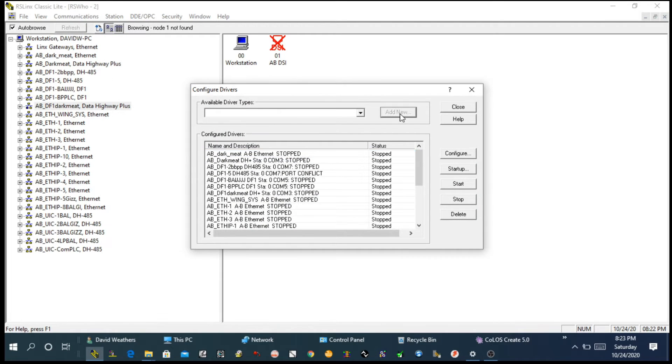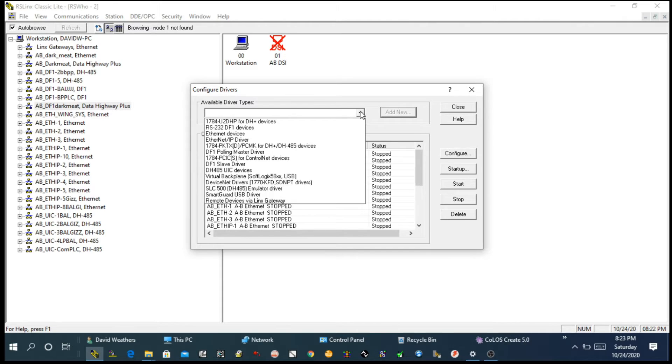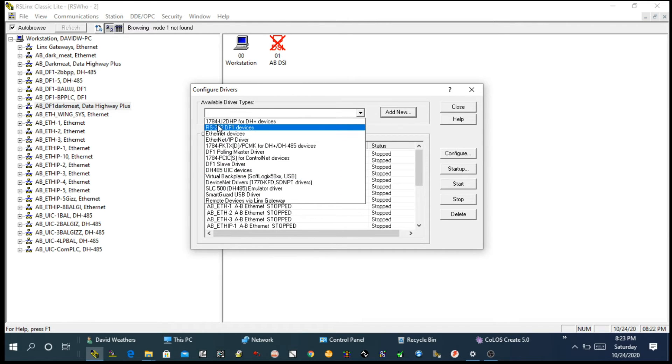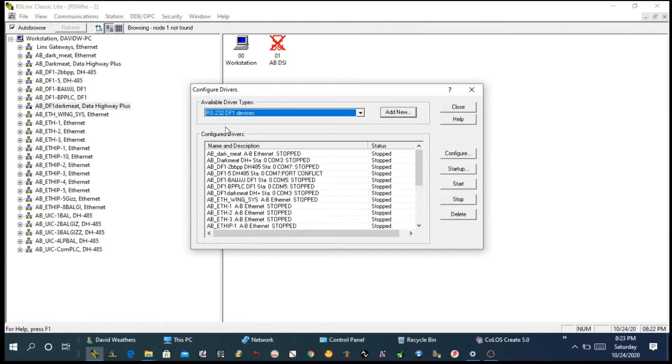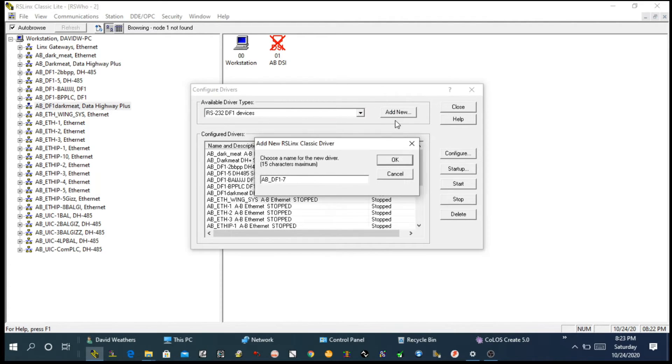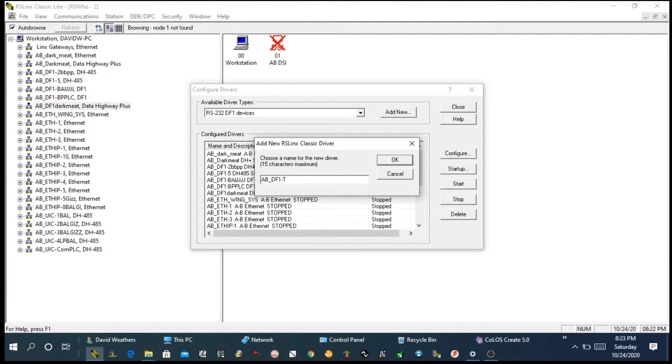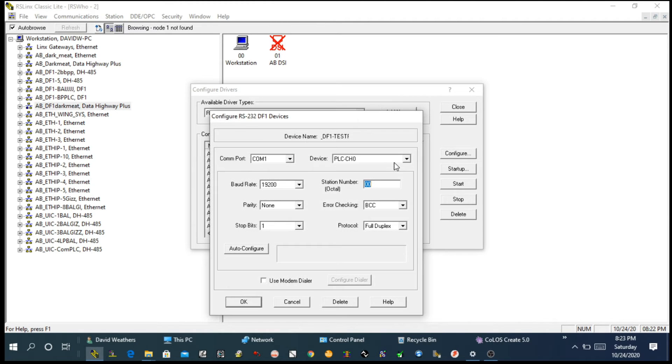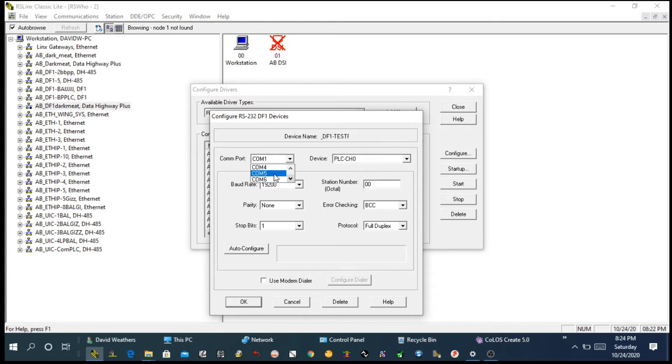From here we have to create a new driver. So I will click on this arrow drop-down menu. I will be using RS232 DF1 device. Choose that one depending on your cable you're using. Then we are going to click on Add New. Once you click on Add New, it's asking for a name. You can leave the default, it doesn't matter. I will put Test here. We are using this driver for testing our PLC. Then you click OK. Over here we have to choose COM port. I'm going to choose COM port number 5.